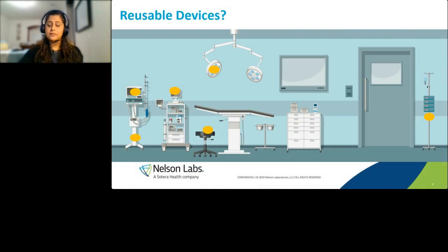These are something that you may not have been familiar with. Do these get cleaned and validated? Sure they do. I mean, you have them in your reprocessing facility's policy to clean them, but are they validated? Do they show that they can remove blood efficiently, protein efficiently? Do we really need to go to that extent? Is visual inspection okay? Where does this fall when it comes to validations? And right now, non-critical devices, which you're seeing here, I've got dots everywhere over here. The yellow dots here, they are, believe it or not, validated for reusability, cleaning, and disinfection. Of course, they can't be sterilized, so they will be disinfected, and it will probably be low-level disinfection. But cleaning is a must. It's not just wiped and you're done with that process.